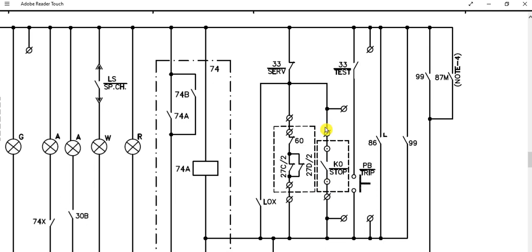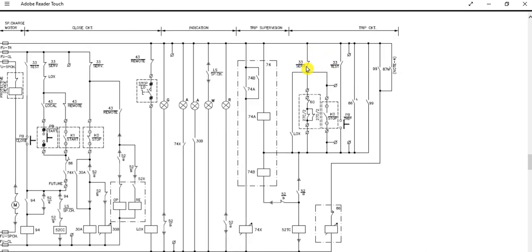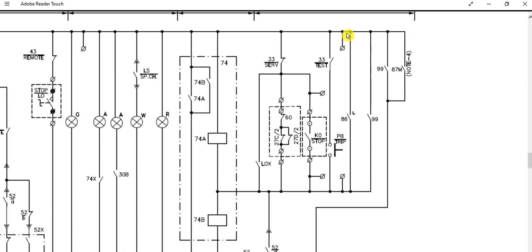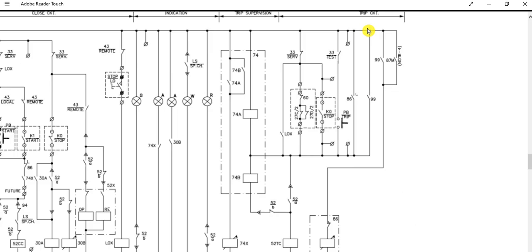Since the circuit breaker is in closed position, this contact is now closed and the path will be followed, and the breaker will get tripped. Additionally, if the 86 lockout relay has operated, it will also energize the trip coil.